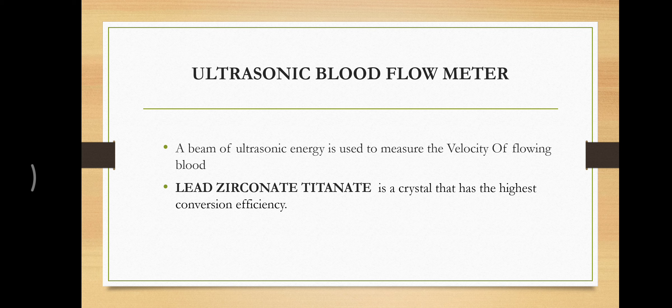Next, ultrasonic blood flow meter. A beam of ultrasonic energy is used to measure the velocity of flowing blood. Lead zirconate titanate is a crystal that has the highest conversion efficiency. Conversion efficiency is the ratio between the output energy to the input energy.